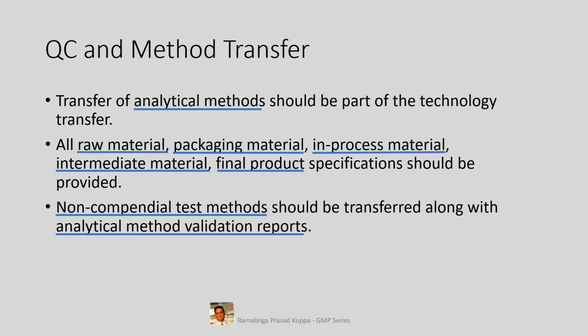The analytical method gets listed in the compendia only after submission of complete validation data, which will be reviewed by a team of experts for compliance. However, it is necessary for verification at RU site for suitability to their laboratory conditions. You need support of USP 1226 chapter for this.